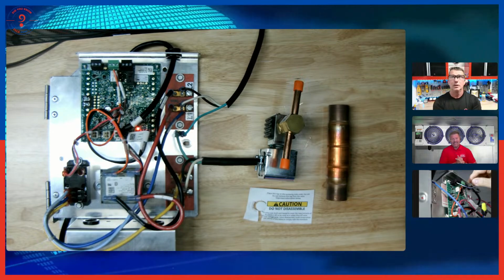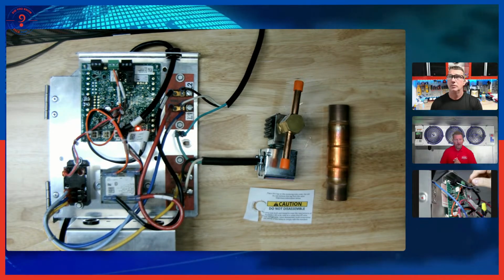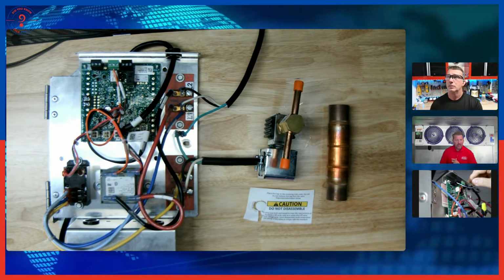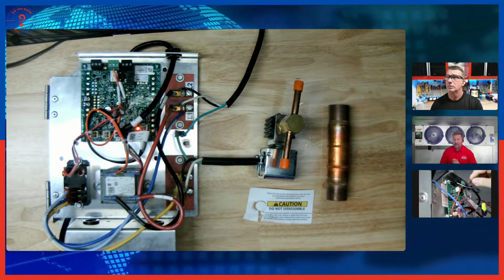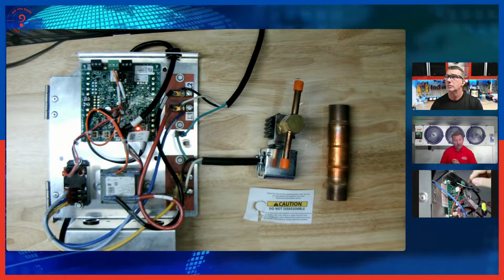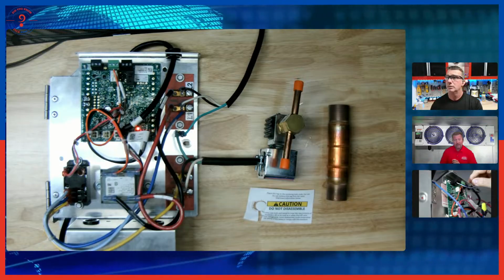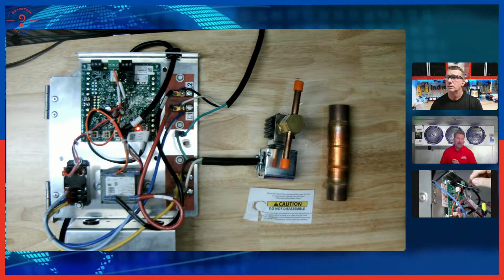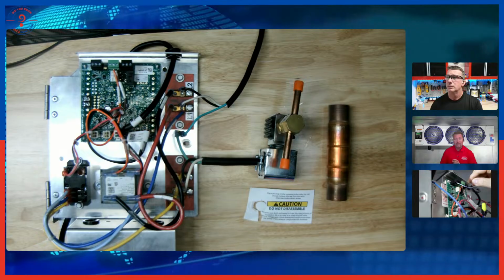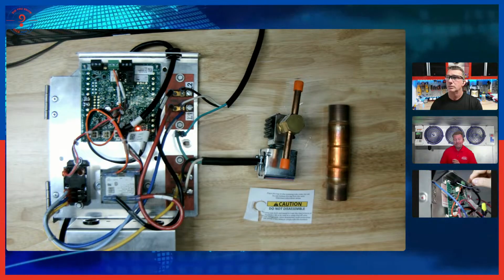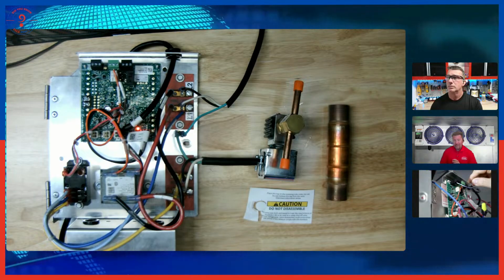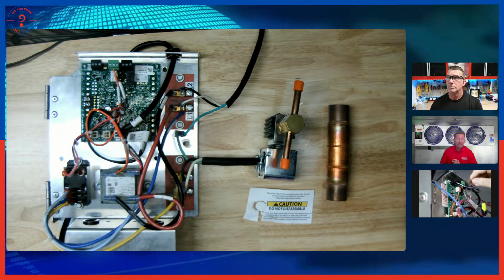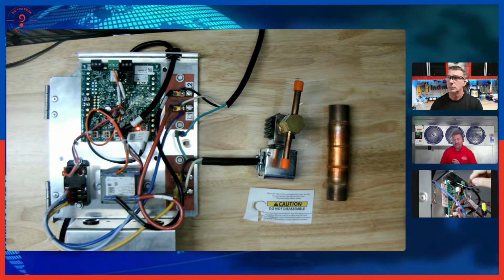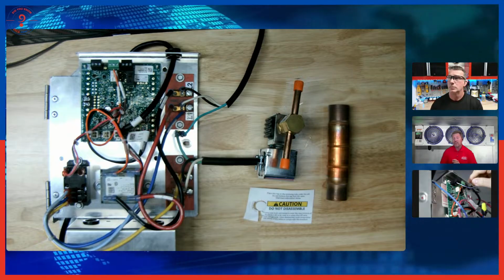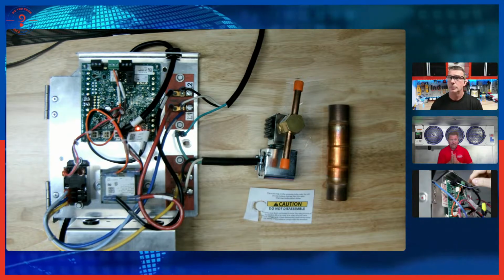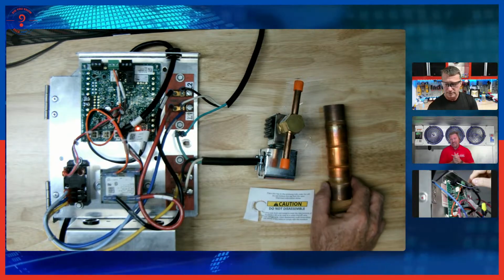No, this is specific for A2L mitigation. There are differences, mainly being this is non-rebuildable. Okay. It is sealed. So, my theory on that, and you may correct me if I'm wrong, is by making it non-rebuildable, we eliminate the possibility of it leaking or being reassembled improperly. This is a safety device. We want to make sure it's as safe as possible. Yep, absolutely.